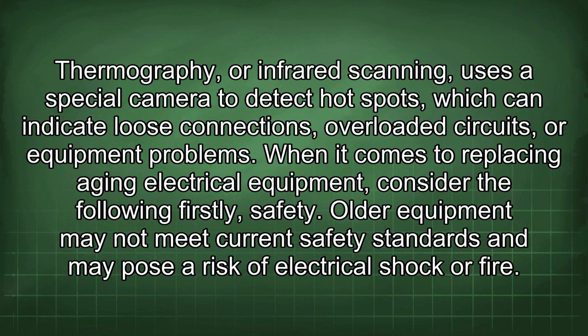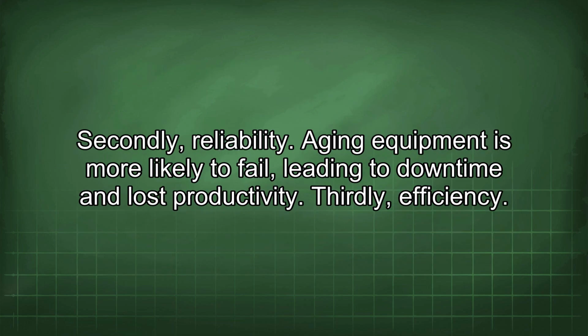Thermography, or infrared scanning, uses a special camera to detect hot spots, which can indicate loose connections, overloaded circuits, or equipment problems. When it comes to replacing aging electrical equipment, consider the following. Firstly, safety. Older equipment may not meet current safety standards and may pose a risk of electrical shock or fire. Secondly, reliability. Aging equipment is more likely to fail, leading to downtime and lost productivity.